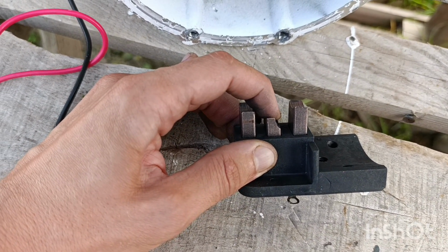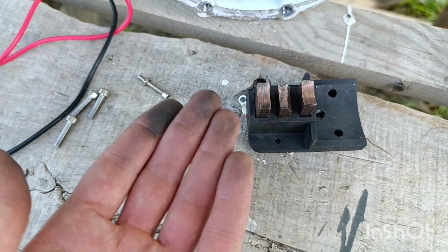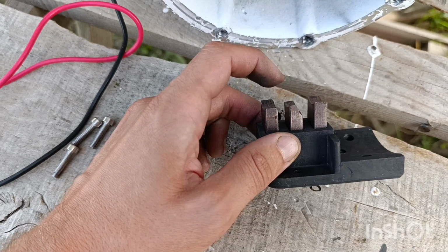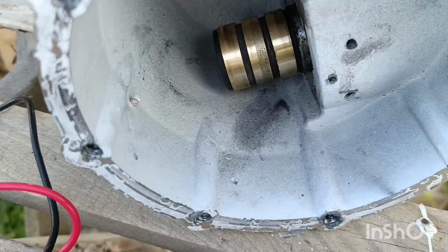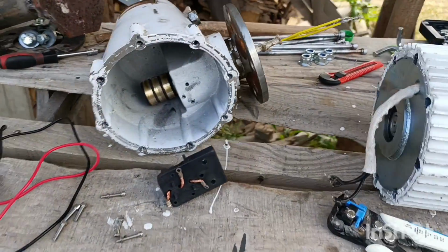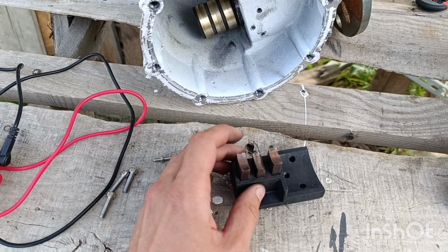and could not go over once it got a little bit worked out. It should be pulled up by the spring, and this thing was not doing it. It was stuck there, and then the arc was happening to transfer the current, because, as I told you, this thing was working absolutely fully nicely until the last day. I was not even aware; it was not giving any noises.